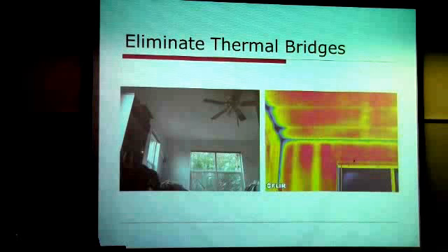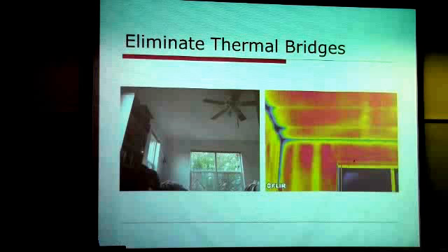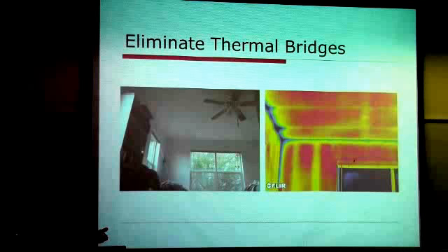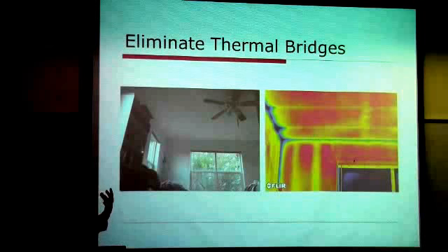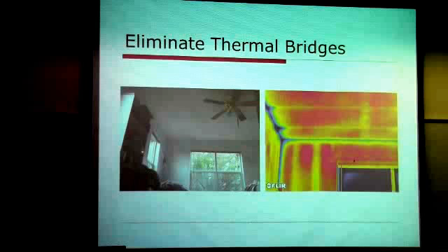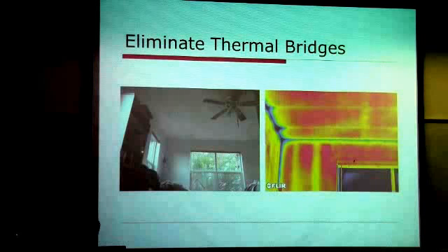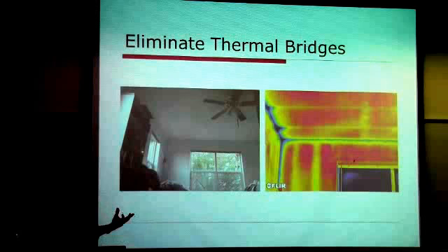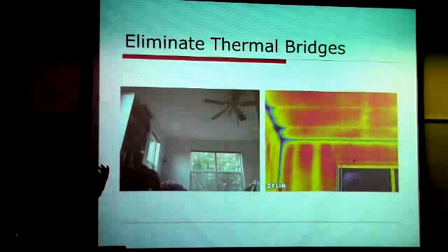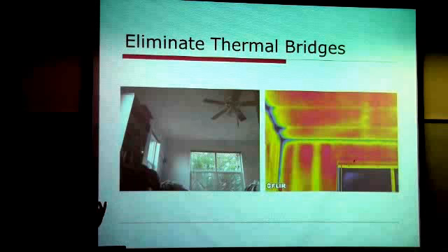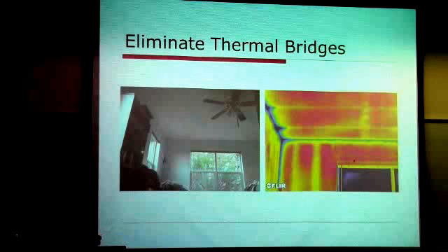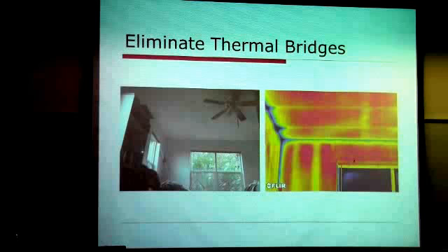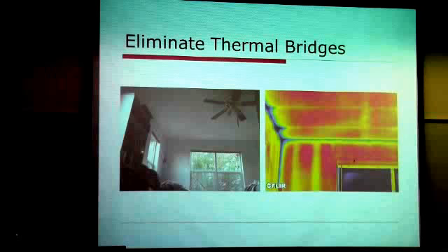So there's generally no moisture problem? No, it's actually, because it stays fresh and it's constant. We have some houses that put what are called towel radiators in the bathroom, just so some people can have a warm towel, and it lessens the number of times you have to wash it since it's clean. That towel radiator will give off heat, get the bathroom up to 72 or whatever, but all that heat will be recirculated to the HRV, and 90% of it will be recaptured and sent throughout the house. So instead of just taking that heat and exhausting it through a regular exhaust system, you're recapturing the heat.